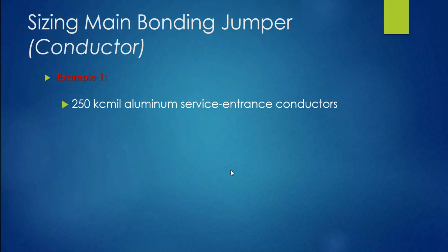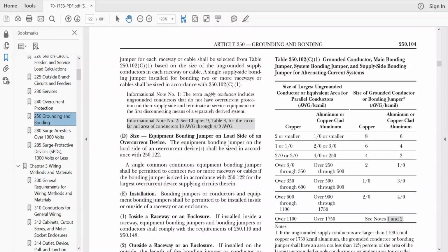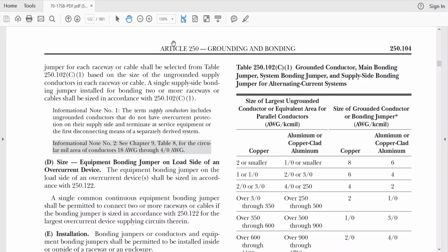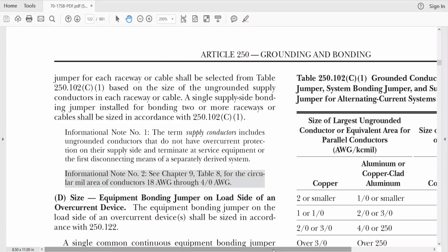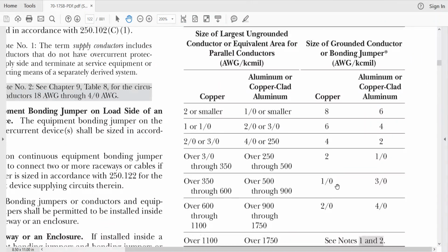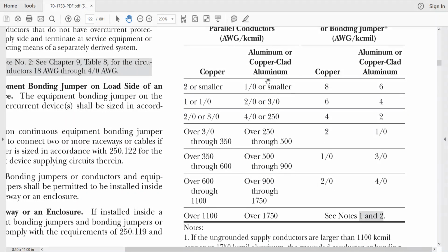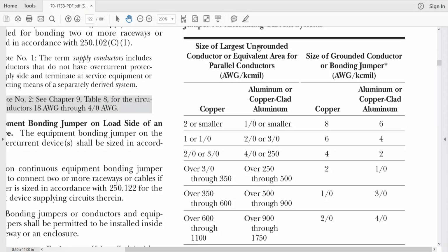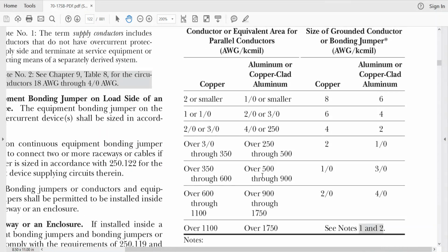The first one, let's say we have a 250 kcmil aluminum service entrance conductor. We just shifted gears here, we went over to aluminum. We have to go to Table 250.102(C)(1) in order to size what we need. All right, so let's go to the code. We know it's 250 aluminum, so let's go to the NEC. Let's make this a little bigger, drag it over here a little bit and go up. What do we have here? We know it's 250 aluminum, so we're in this column. It says the size of the largest ungrounded conductor or equivalent area for parallel conductors. In this case down here, we said it was 250 aluminum.